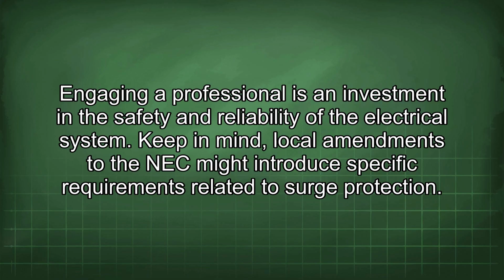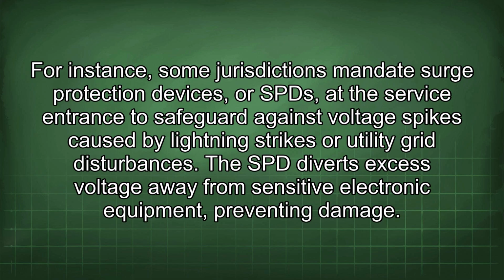Keep in mind, local amendments to the NEC might introduce specific requirements related to surge protection. For instance, some jurisdictions mandate surge protection devices, or SPDs, at the service entrance to safeguard against voltage spikes caused by lightning strikes or utility grid disturbances. The SPD diverts excess voltage away from sensitive electronic equipment, preventing damage.